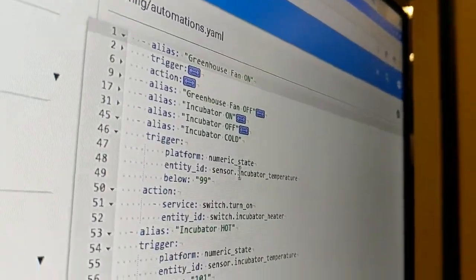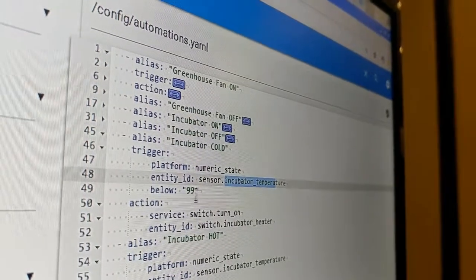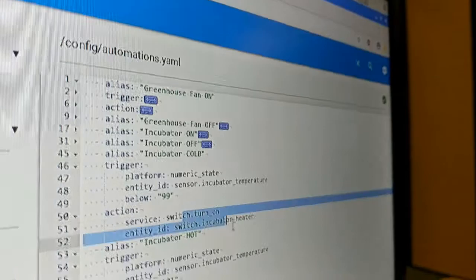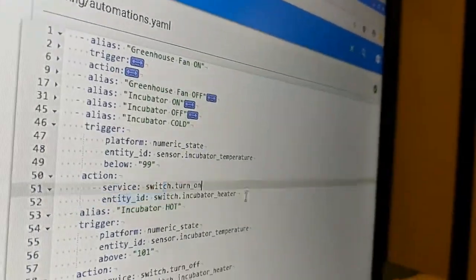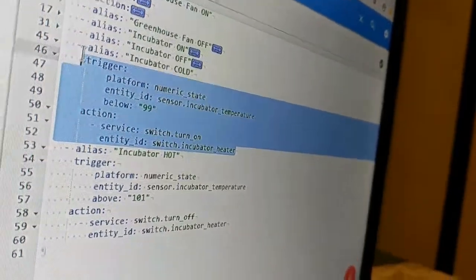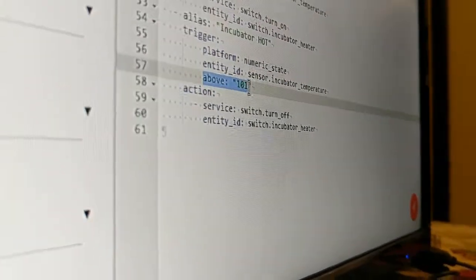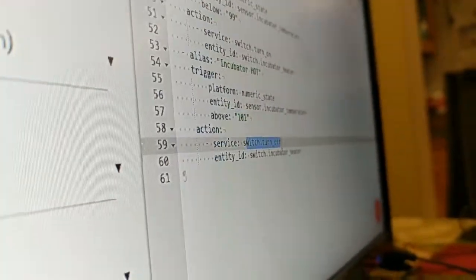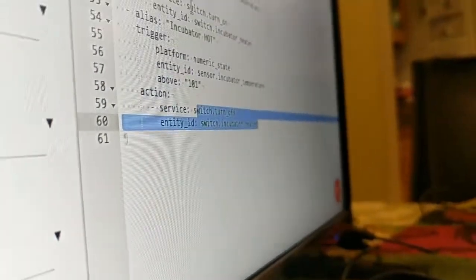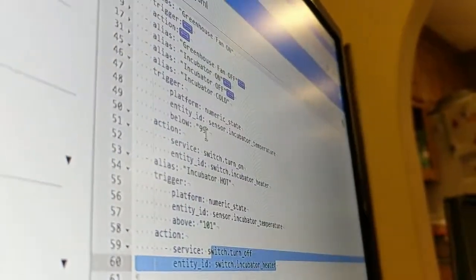Basically, this one says if the incubator temperature is below 99 degrees, turn on the incubator heater - that's the trigger. The next one says if the incubator temperature is above 101 degrees, turn off the incubator heater. When we originally wrote this, we had it set to below 100 turn on, above 100 turn off.